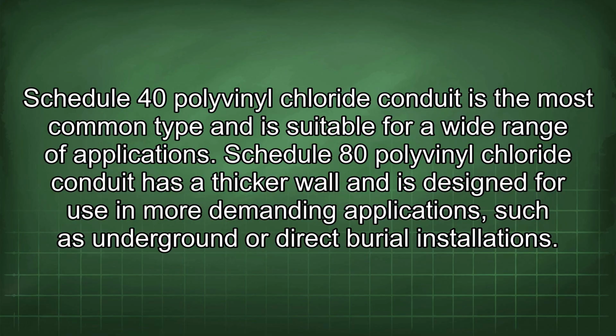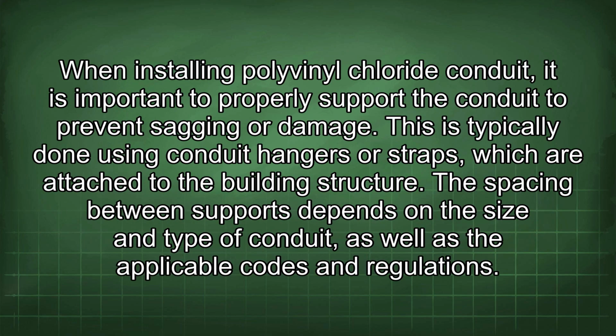Schedule 80 polyvinyl chloride conduit has a thicker wall and is designed for use in more demanding applications such as underground or direct burial installations. When installing polyvinyl chloride conduit, it is important to properly support the conduit to prevent sagging or damage. This is typically done using conduit hangers or straps, which are attached to the building structure. The spacing between supports depends on the size and type of conduit, as well as the applicable codes and regulations.